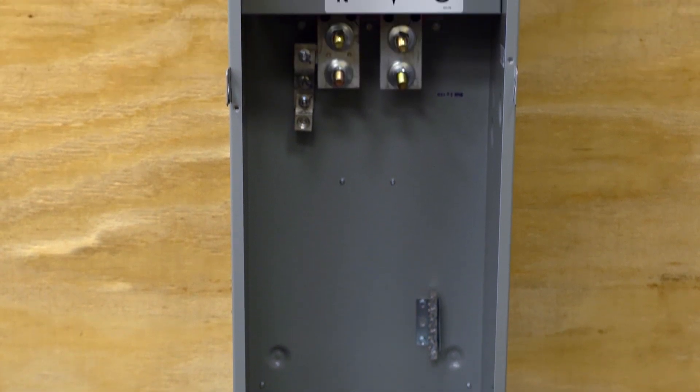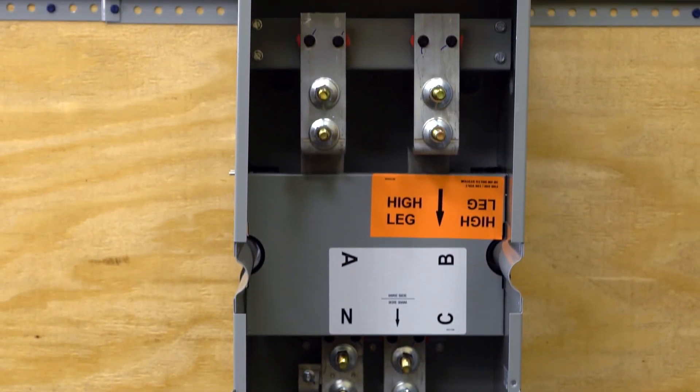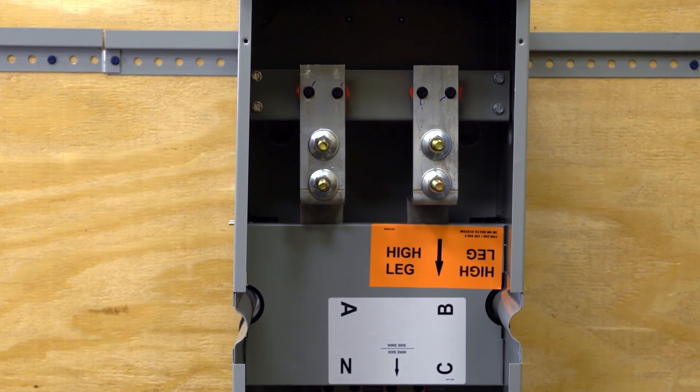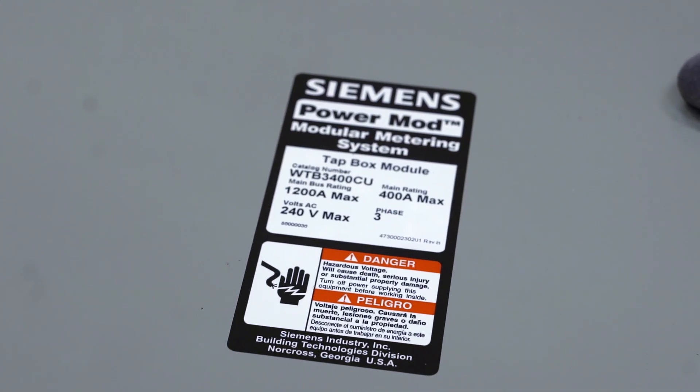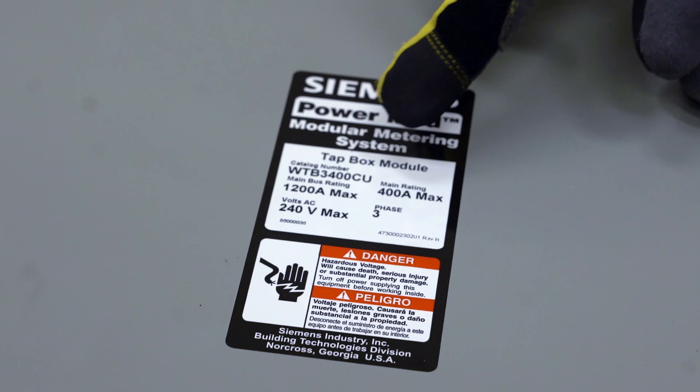If you're unsure from which direction you'll be feeding your mains or tap boxes, it is best to use combination feed modules so that you can make that decision in the field. The C and CU suffixes in the catalog number indicate that unit can be fed from overhead or underground.